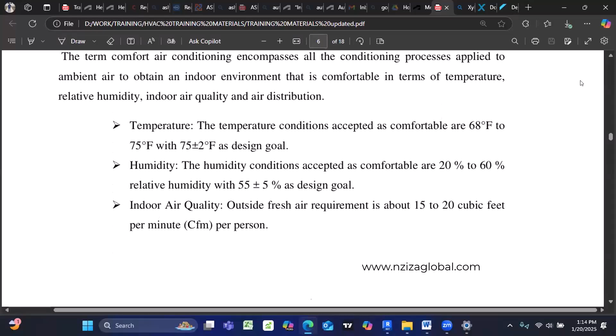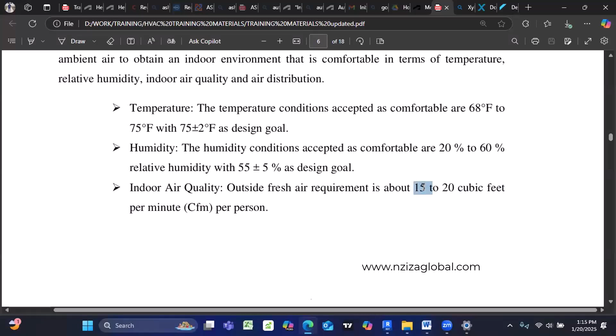The humidity acceptable as comfortable ranges from 20% to 60%. Here the design goal is 55 plus or minus 5%. Also, indoor air quality: the outside fresh air requirement for comfort is 15 to 20 CFM. CFM is cubic feet per minute in imperial units. So when you obtain 15 to 20 CFM per person, that is considered comfortable.